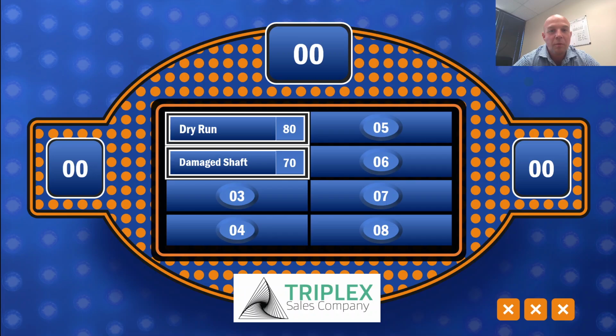And both in the Universal 1, Universal 2, and Universal 3, we'll have a shaft O-ring, okay? And if there is damage to that groove on the shaft, what we can see is we can start to see those shaft O-rings rip up or fail or tear upon installation shortly after use, just because of damage done to the shaft through the course of regular use and normal wear and tear.